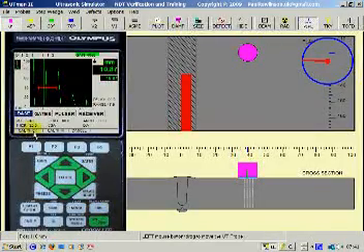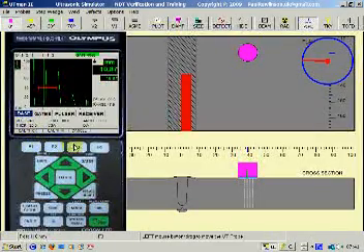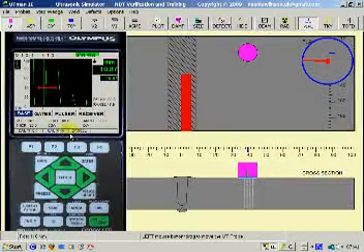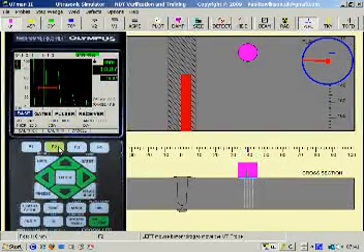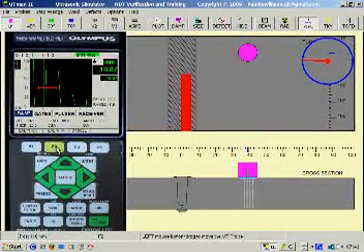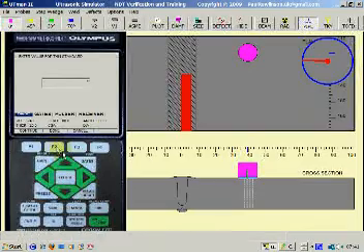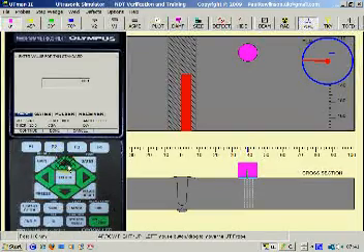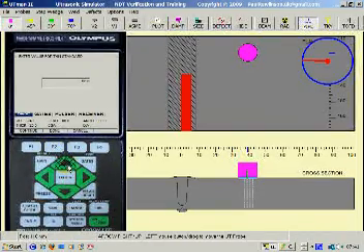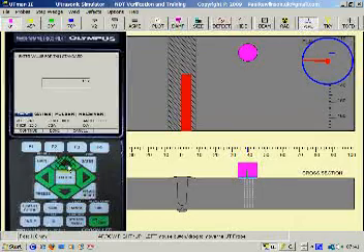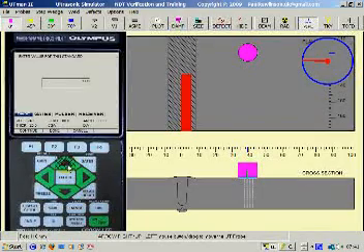And we've got this help now on the F1, F2, and F3 keys. CAL thick, CAL thin, and cancel. I will click on CAL thin, F2, enter the reading, which is 20, which is a 20 millimeter thick plate.